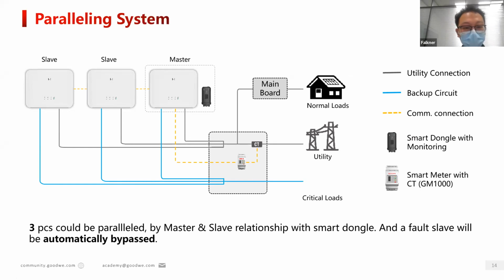In this system, one inverter will be the master and two will be the slaves. They will connect together both the on-grid side and the backup side. And the faulty slave will be automatically bypassed. In this solution, there will be some requirements. You can find the document on our website. I will show you some. First, the backup side line should be a similar length, and the battery connected to each inverter should be the same capacity, and they should be charged or discharged at the same time.